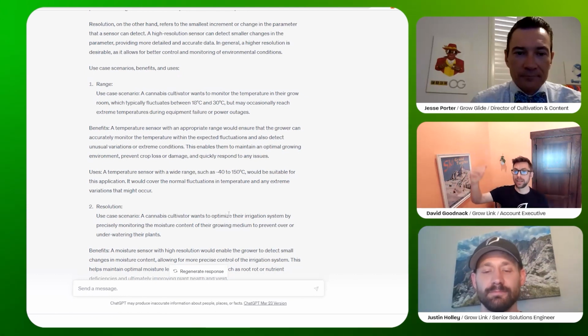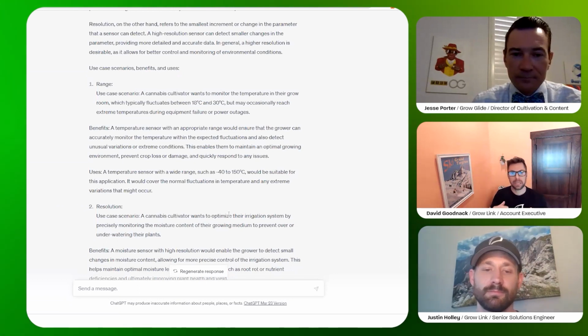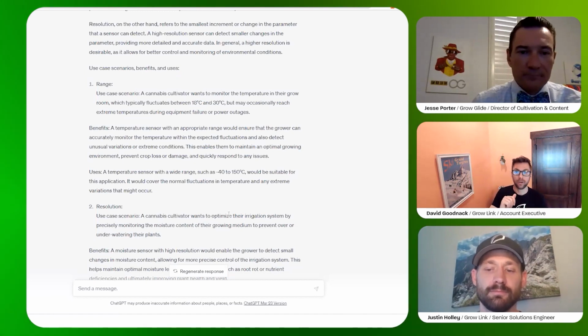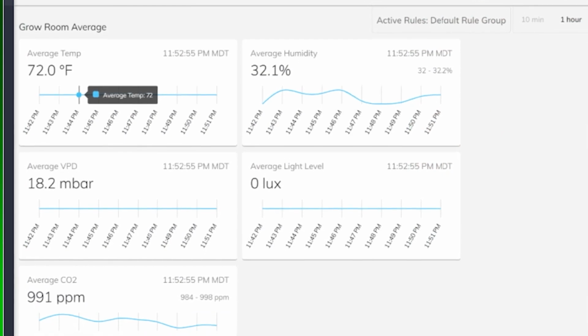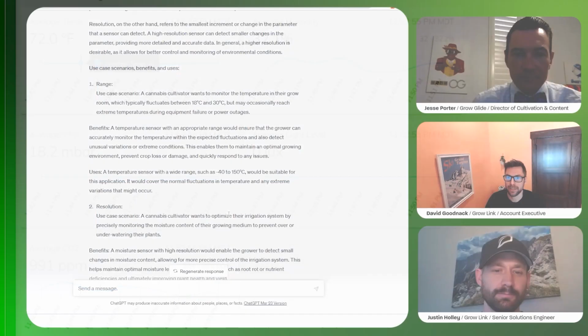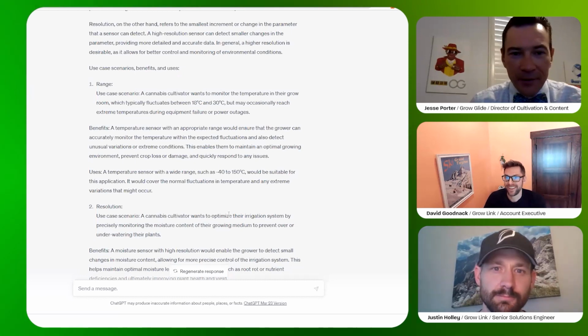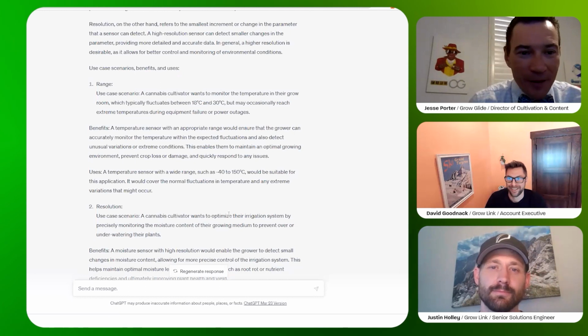And then third stage is buy what you should have bought, which is an HVAC plus D unit, which you can manipulate fan speeds, compressor speeds, everything to be able to dehumidify and cool or dehumidify without cooling, right? And maintain that with the least amount of energy, least amount of inputs, which the guys that go with that, they're thanking themselves later. Just by having very well controlled spaces, as well as the operational savings, which, if you went with that first when you had all the money, you're probably doing okay right now. You don't think about the cost of downtime or compressor replacements or fan replacements until you have to do it.